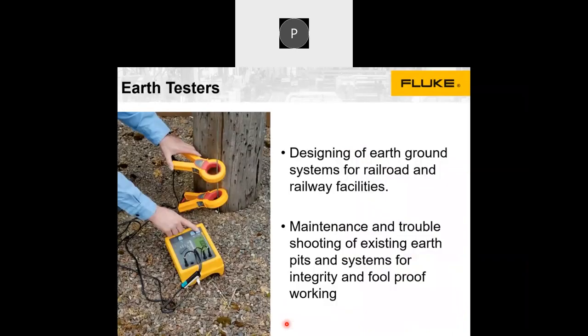As I said, the earth testers are important because earthing means designing of earthing and ground systems for railways or any facilities, whether it's railway, a house, a commercial building, or a factory. Earthing is actually the base for every electrical, signaling, or communication system. If that is not good, you may not be able to find the real reason for failures. That's why designing and maintaining earthing is very critical for all kinds of railway applications.